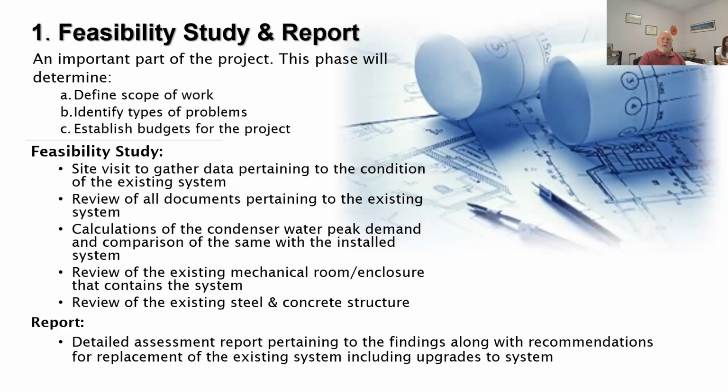Well, as I've said, code changes through the years. If your cooling tower is even 10 years old, the wind loading that it requires is significantly higher. And because the wind loading is significantly higher, the weight of the equipment is significantly higher. And when the weight of the equipment is significantly higher, your existing structure needs to be thoroughly evaluated to make sure that it actually can withstand the weight that the new tower takes in.